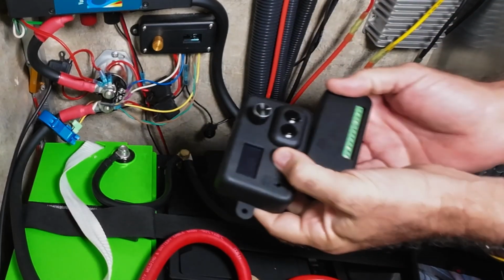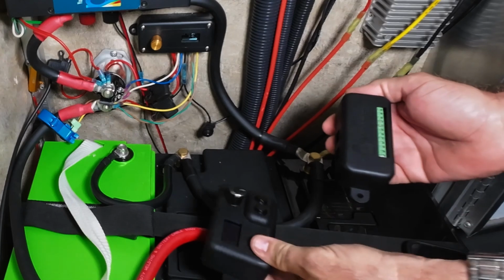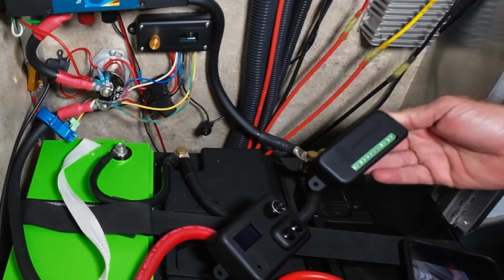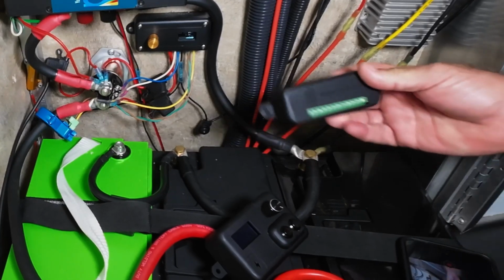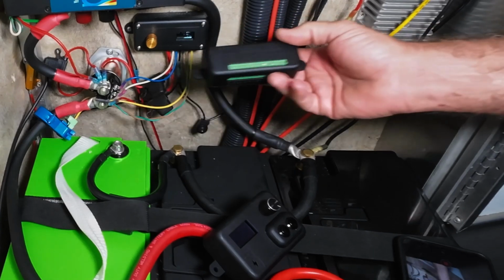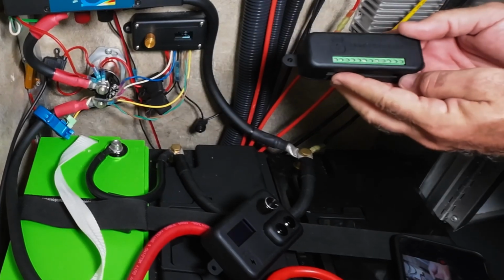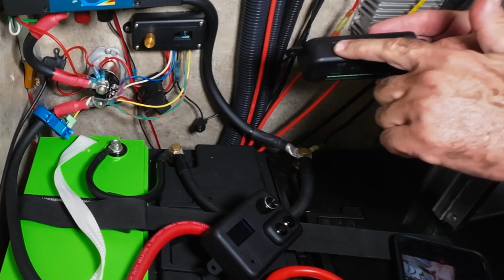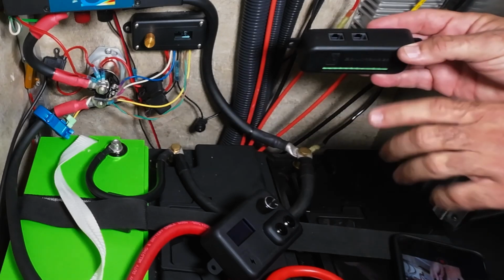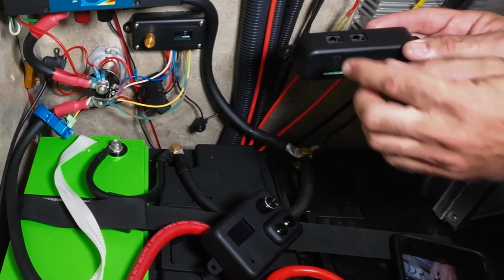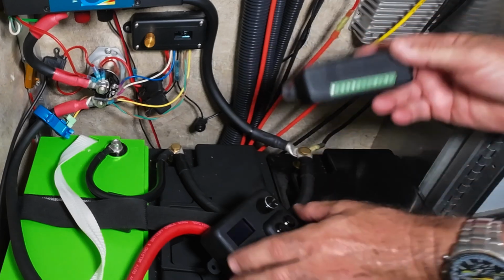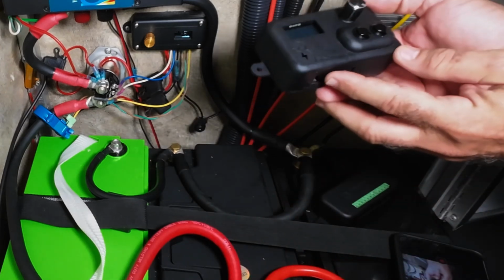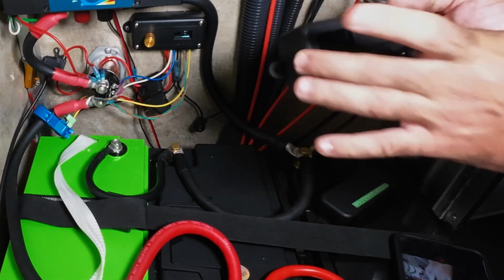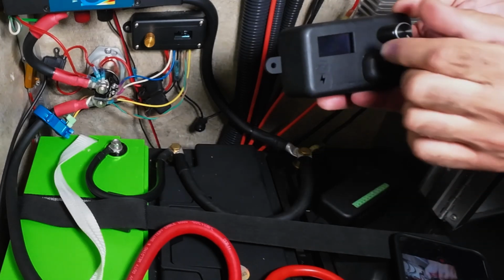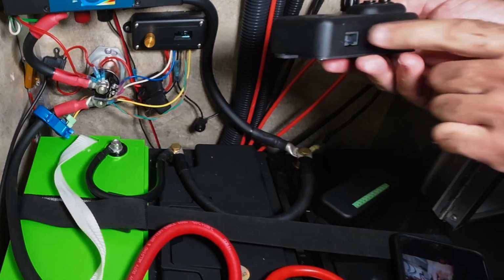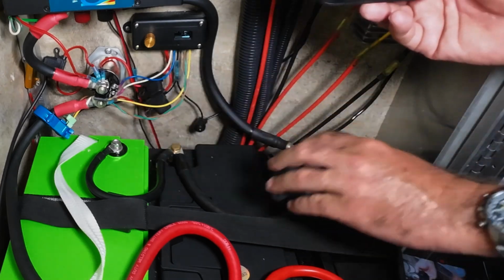This version of the BankManager Gen 3 is what we call the surface mount. It has 2 boxes. This one goes where all the wires go, close to the batteries, and it picks up all the information and sends it out over Ethernet cables, not Ethernet topology, just using the cables to the display unit. The display unit has the microprocessor in it and all the real workings and the real magic, and it uses those Ethernet wires to control what happens in the outside world.